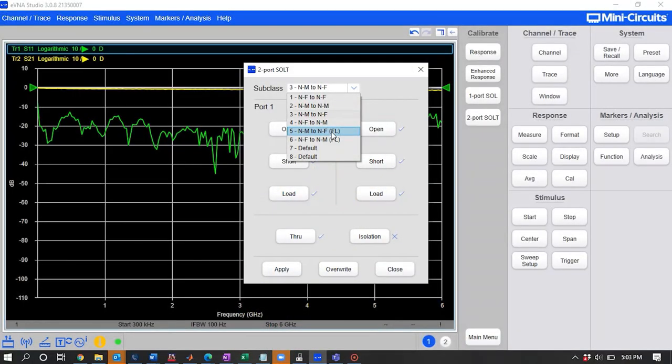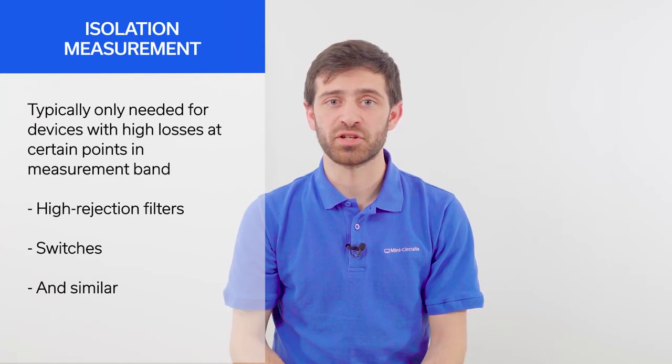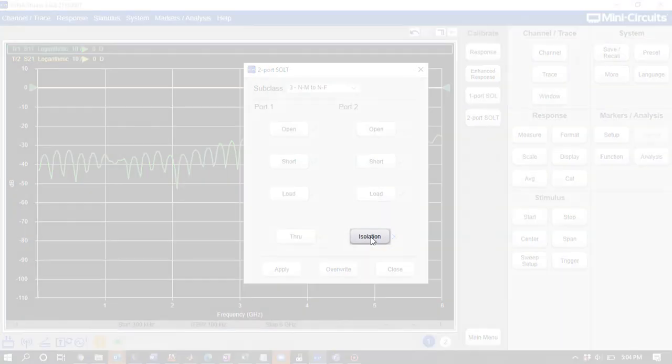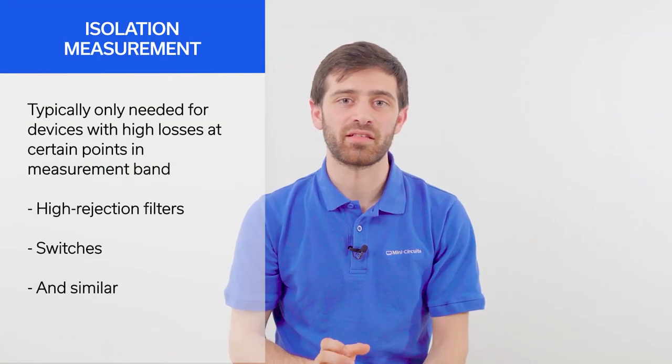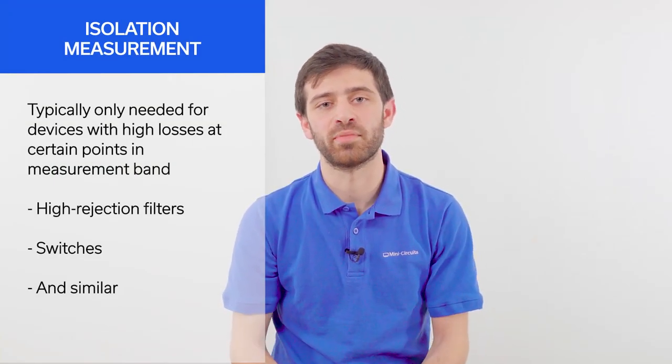Those subclasses are denoted with an FL in the drop menu. We can make the isolation measurement by terminating both ports and taking the measurement. Note that the isolation measurement is optional and should only really be used for DUTs with high losses at some points in the measurement band, like some high rejection filters or switches in the off position.